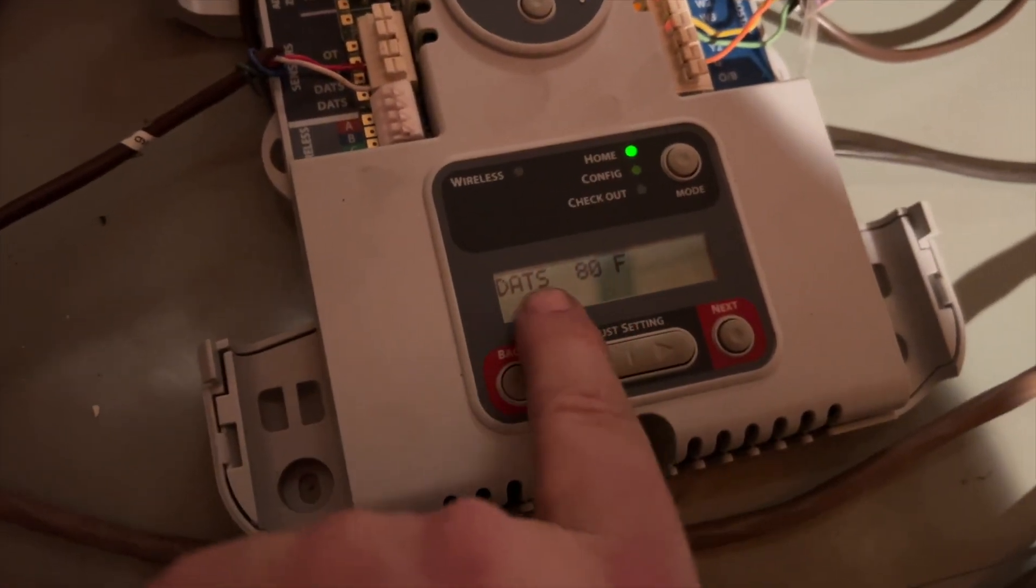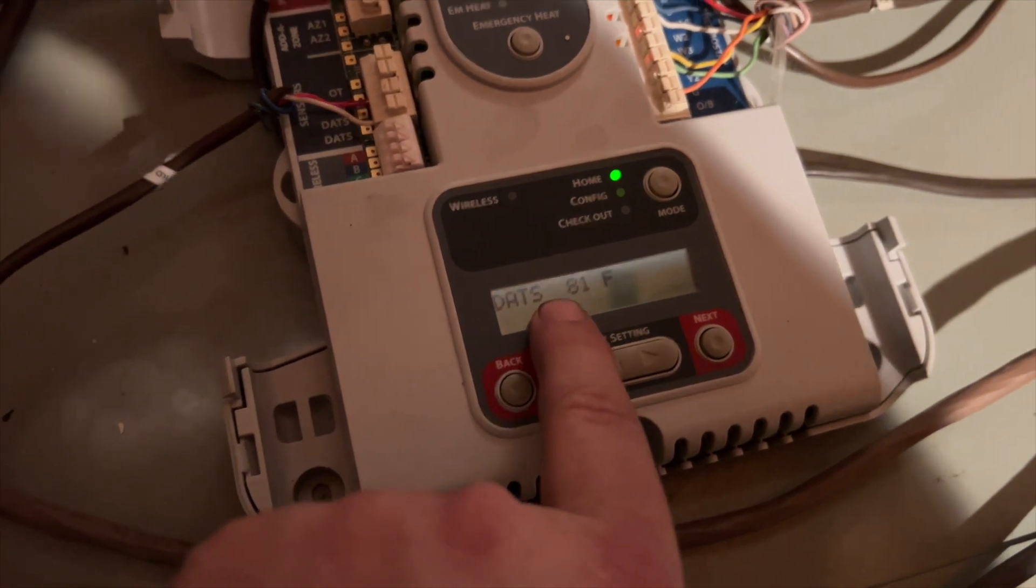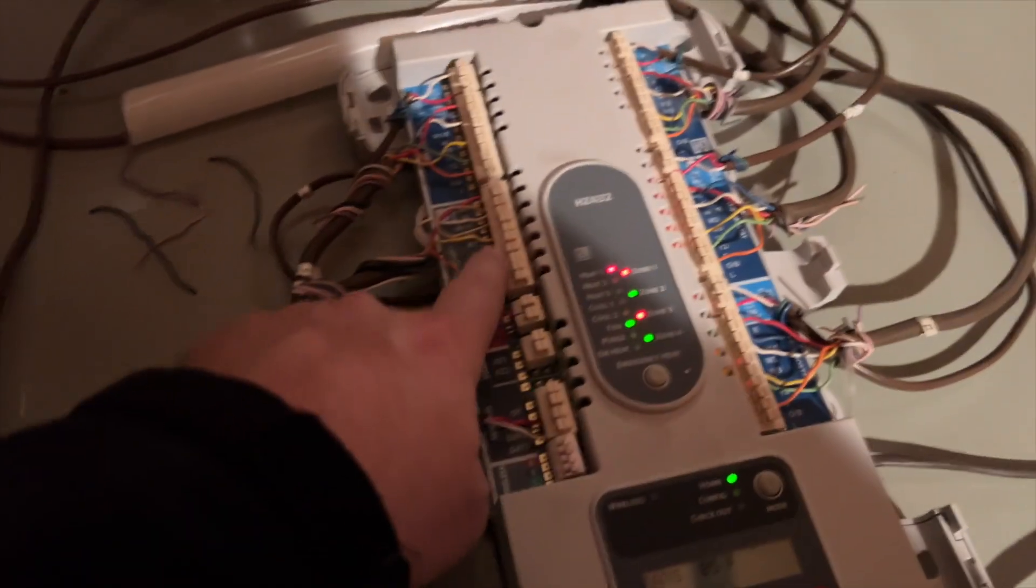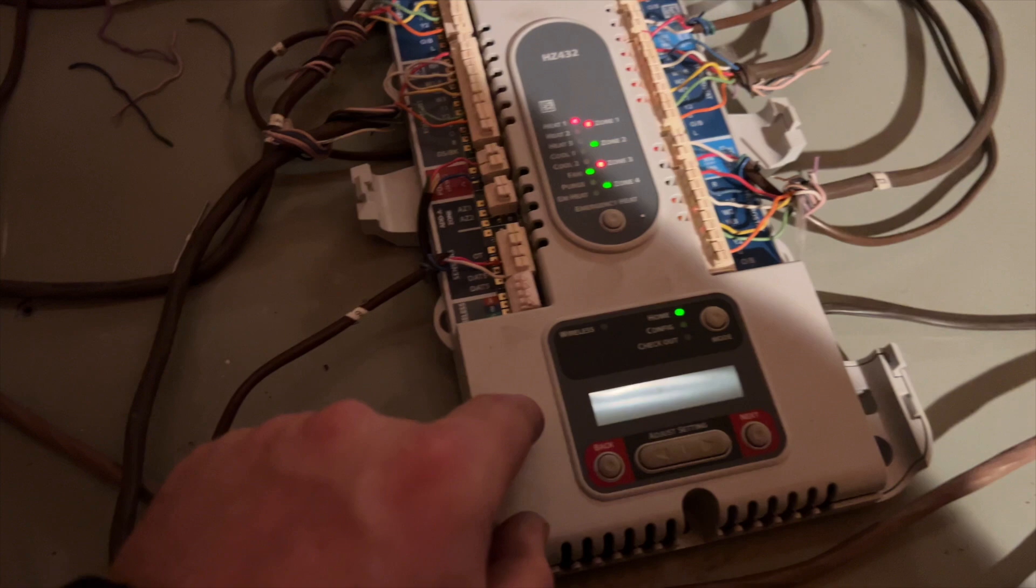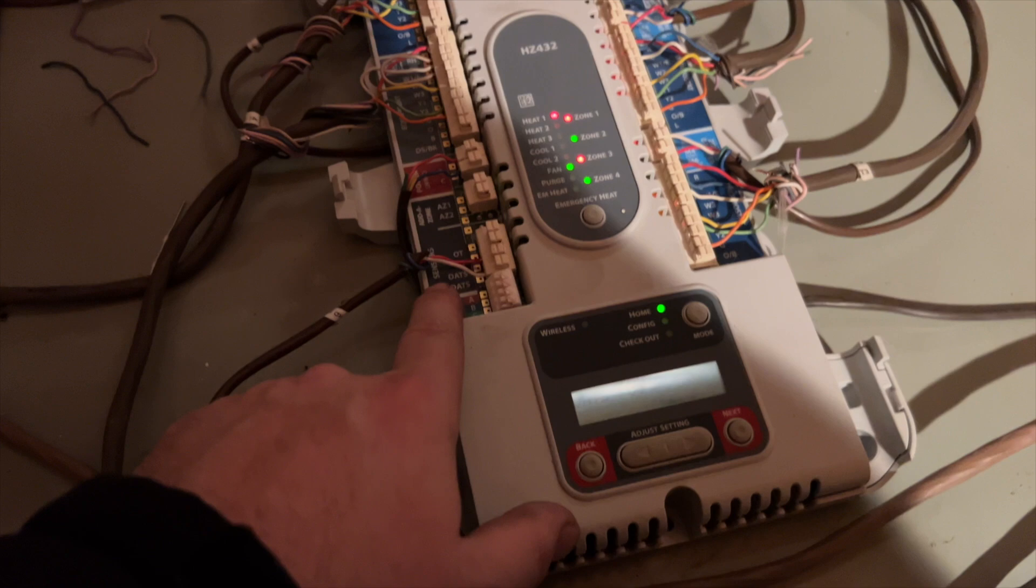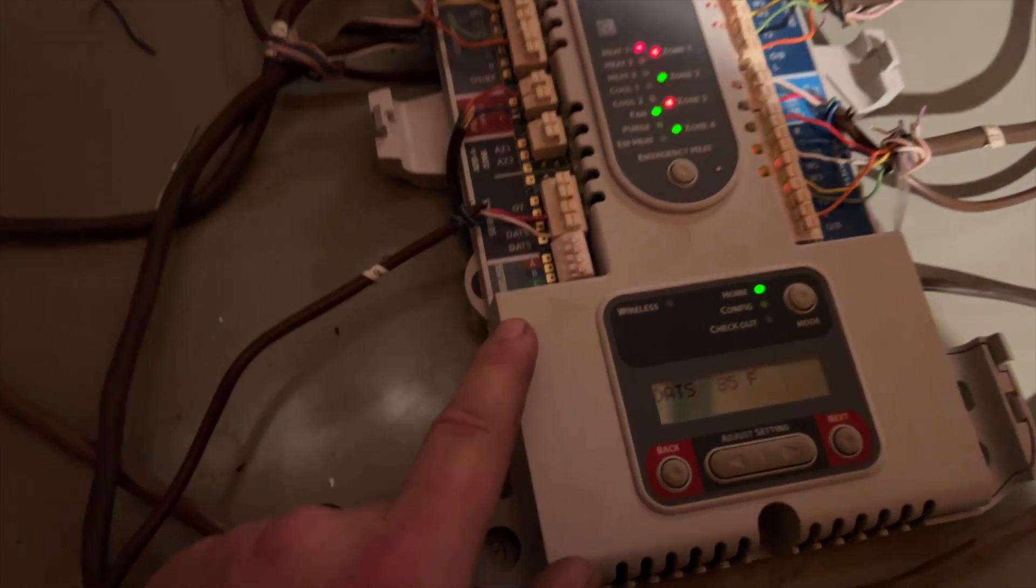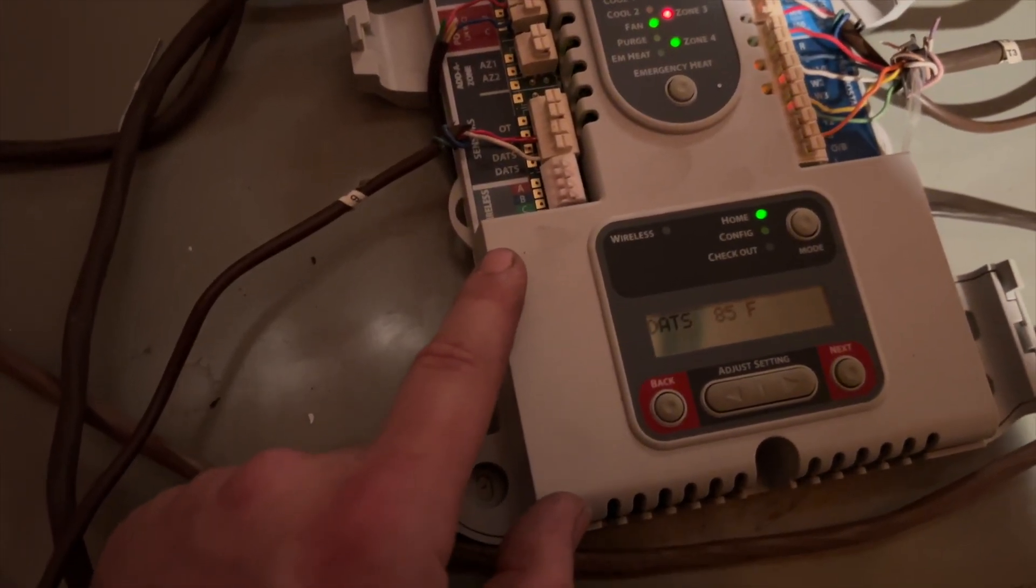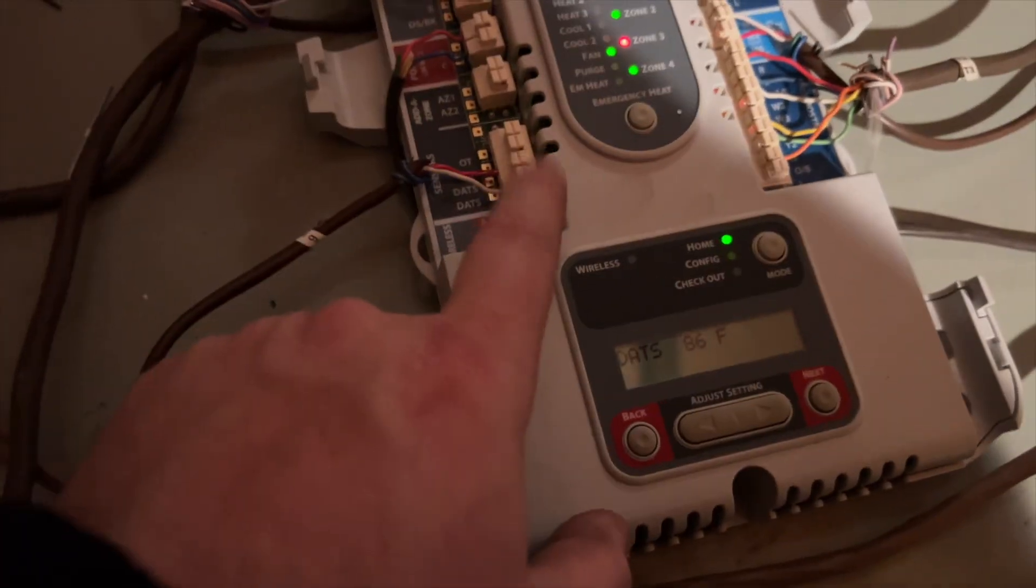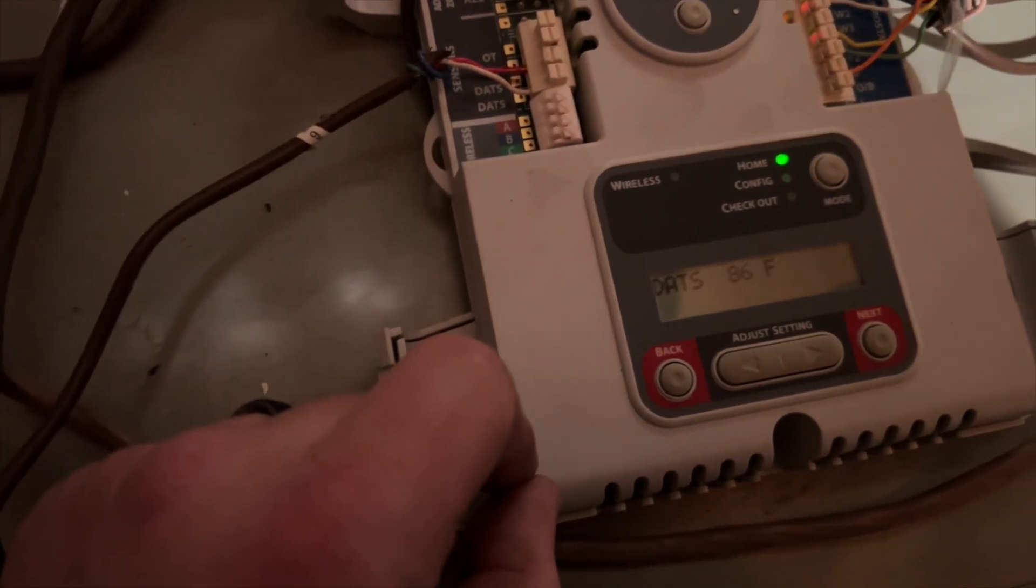Right here, this is our screen DATS - that's our discharge air temperature sensor. It's detecting 81 degrees Fahrenheit. So zone 1, 2, 3, and 4. This is going to the equipment. That's our 24 volts from our transformer. This is our DATS. And you can hook up an outdoor temperature sensor, and then you can also hook up the wireless thing right here too. And then that outdoor will go here on the two OTs.